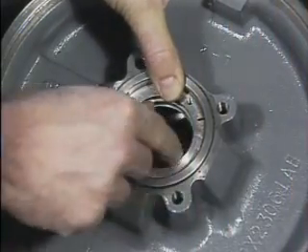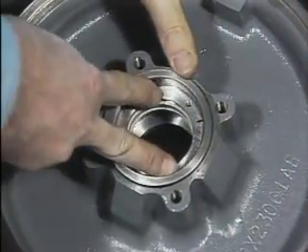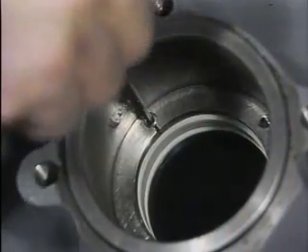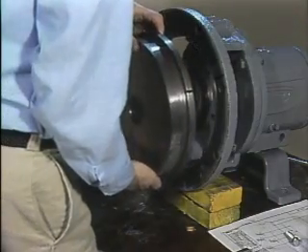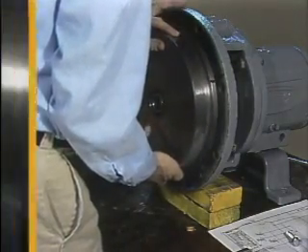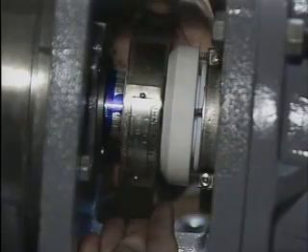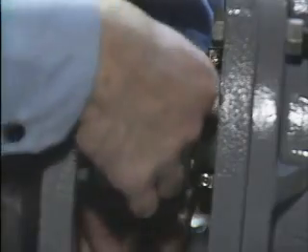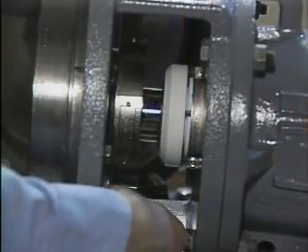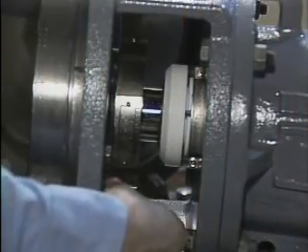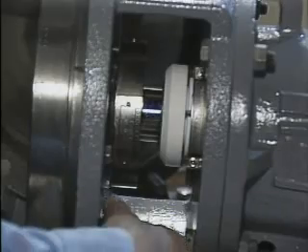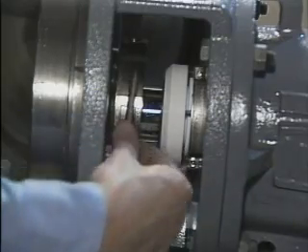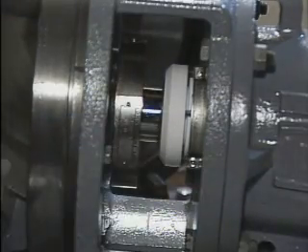Now the back plate is prepared for installation. First, the bushing is inserted into the stuffing box and secured with a screw. Then the back plate is installed on the pump frame. Next, the gland plate is slid into position, and the cap screws that hold it in place are tightened. Then a feeler gauge is used to measure the gap between the gland plate and the back plate to make certain that the gland plate was tightened properly.